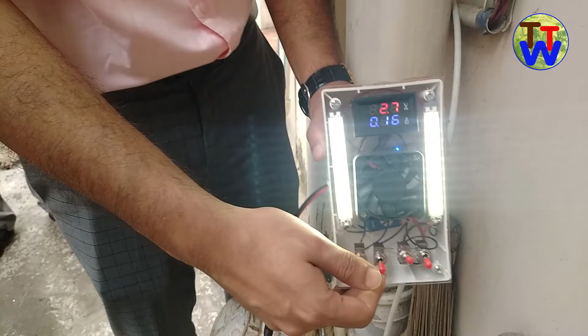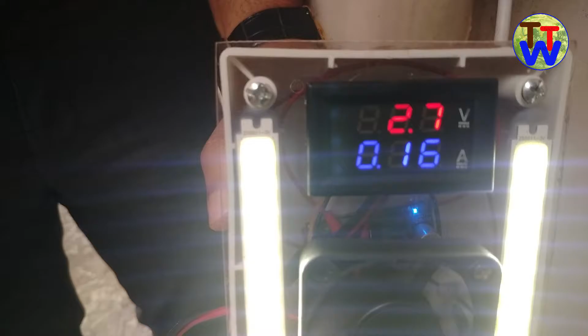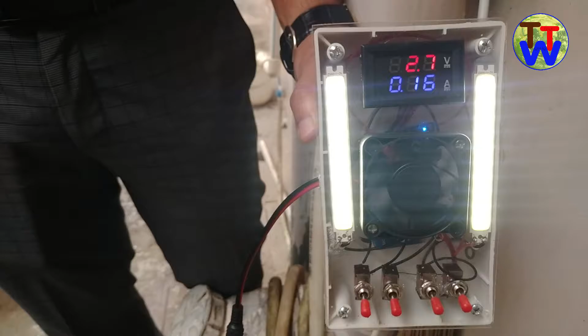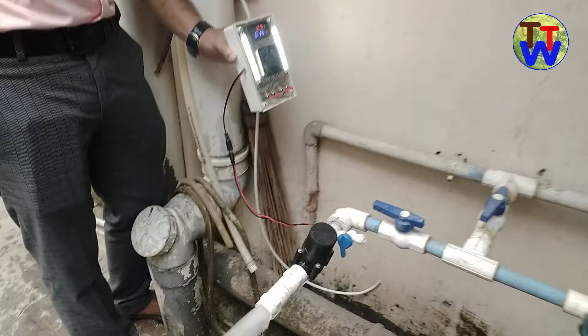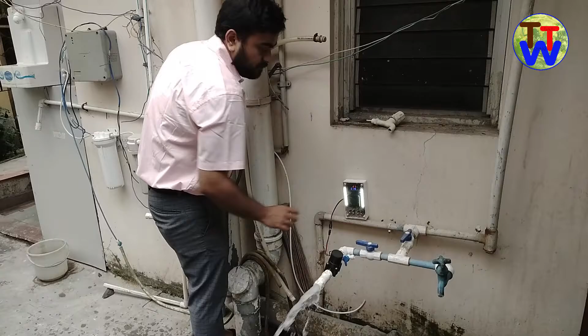you can turn one light, it will turn on, the voltage will drop drastically. As you can see, it will drop to 2.8, and it will not work at the rated voltage. Why? Because it will draw a very huge amount of current which the generator cannot supply. So it's drawing about 160 milliamps of current at 2.7 volts. So you can see the load which was earlier working at 12 watts. Now if you multiply 2.7 by 0.16, you will get about 0.4 watts.